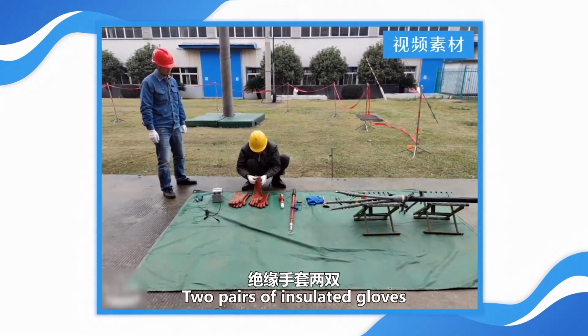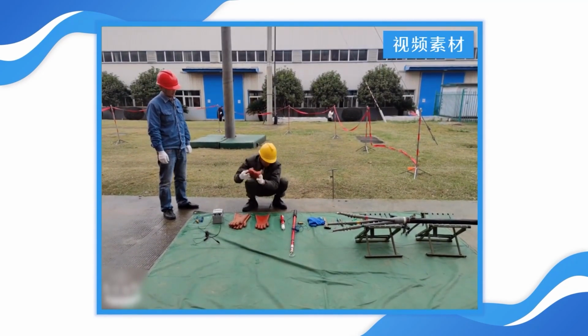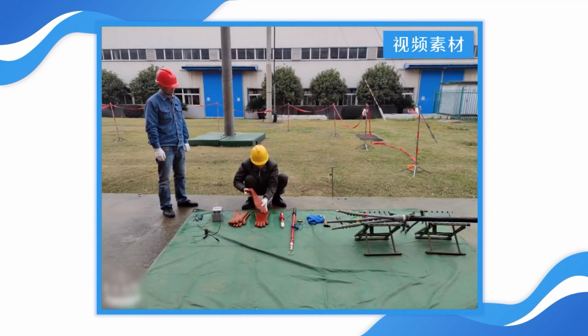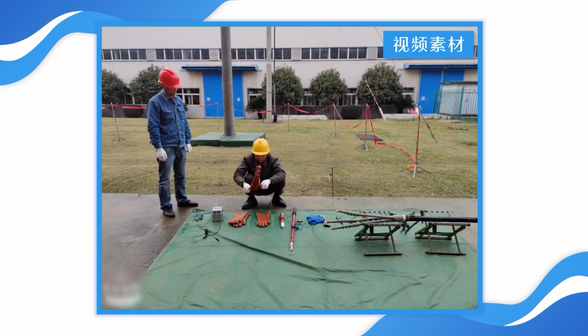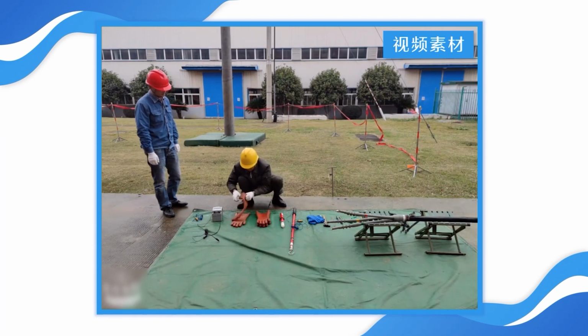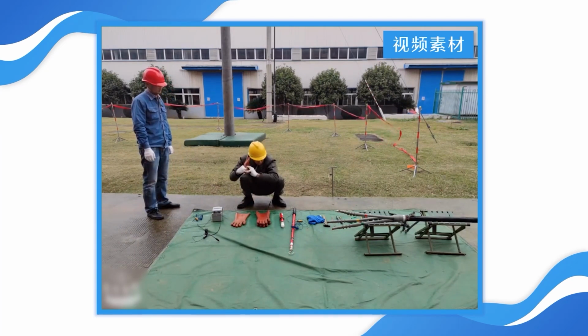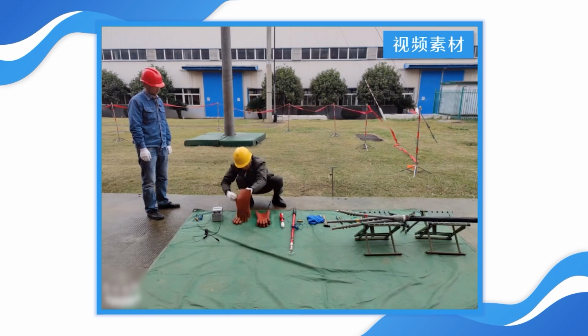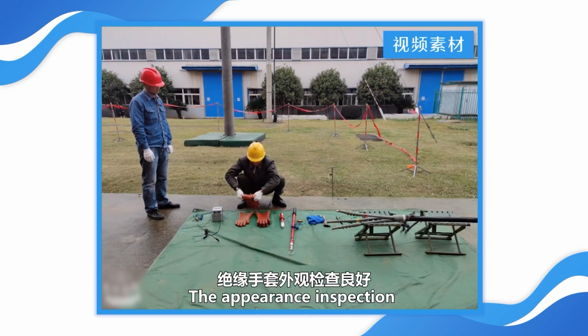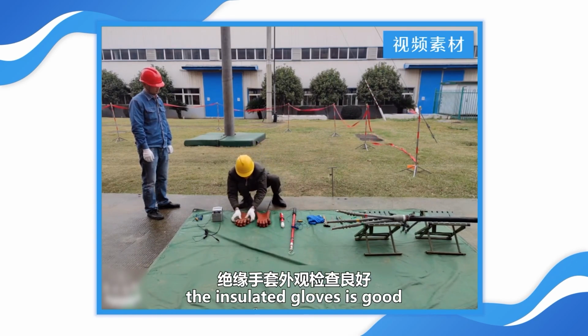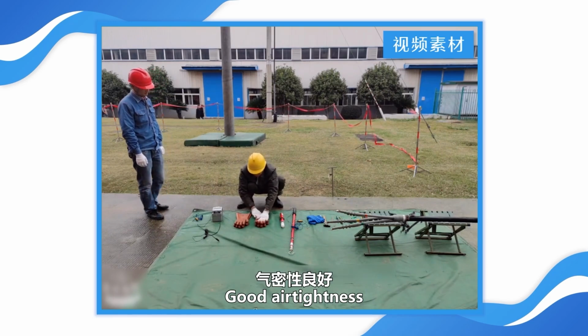2 pairs of insulated gloves. The appearance inspection of the insulated gloves is good, with good air tightness.